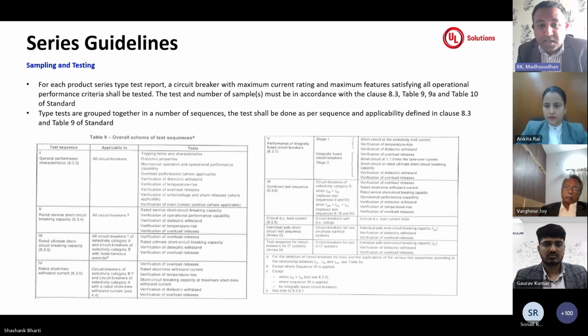In the next slide, I'll give you a brief view of the sequences that are going to be covered based on your declarations. With respect to these sequences, tests have to be conducted, and based on the acceptability of results, the product can be covered under that particular range. So any construction break you declare has to undergo the sequences of tests. For each sequence, the standard allows you to use different products, and it does not require using a single product for all the sequences. So for sequence 1, you can use a separate sample.